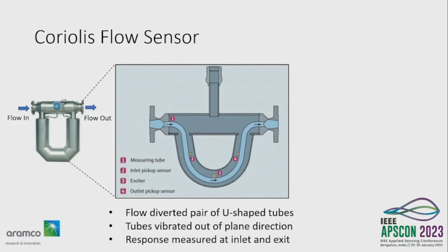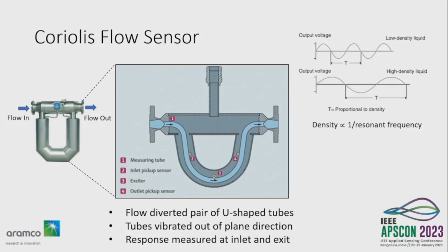If you have not seen one, it looks like that on the picture there. The flow of the liquid or gas is coming in the left. It goes through the U-shaped tube and it comes out. If you cut away the outer metal section, this is what you will see inside. Point 3, right in the middle of the U, is an exciter which vibrates the U-shaped tubes out of the plane. And there are two pickups that measure the vibration response of the tube, one at 2, which is at the inlet side, and one at 4, which is at the outlet side.